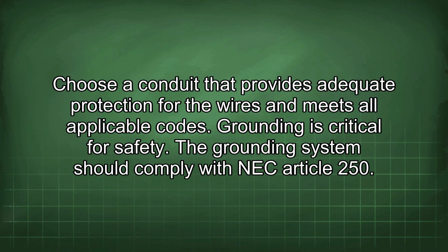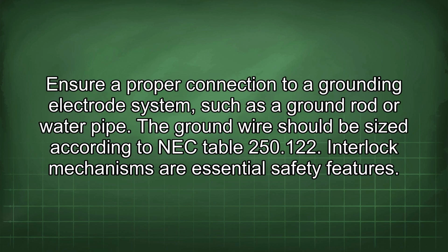Grounding is critical for safety. The grounding system should comply with NEC Article 250. Ensure proper connection to a grounding electrode system, such as a ground rod or water pipe. The ground wire should be sized according to NEC Table 250.122.